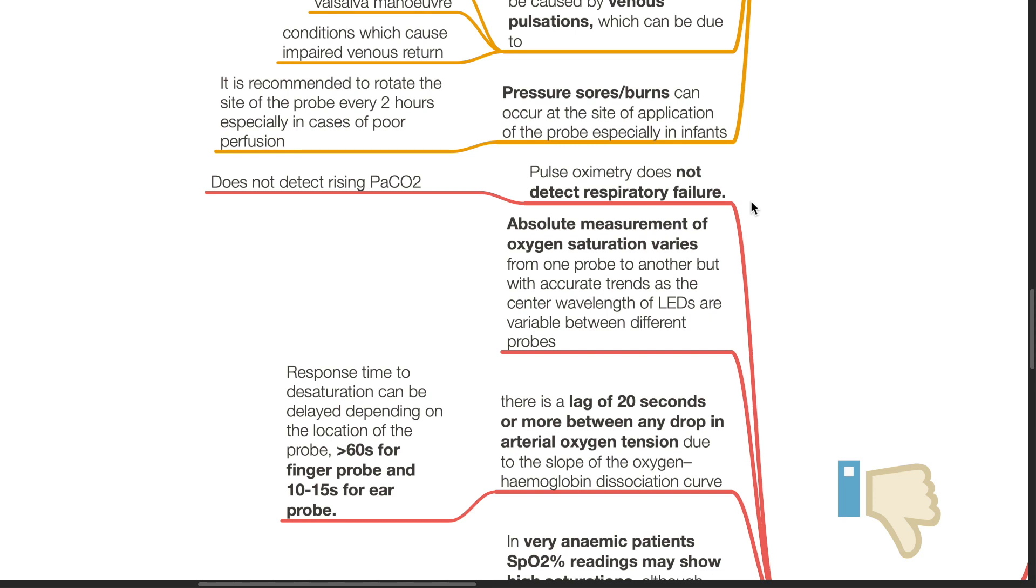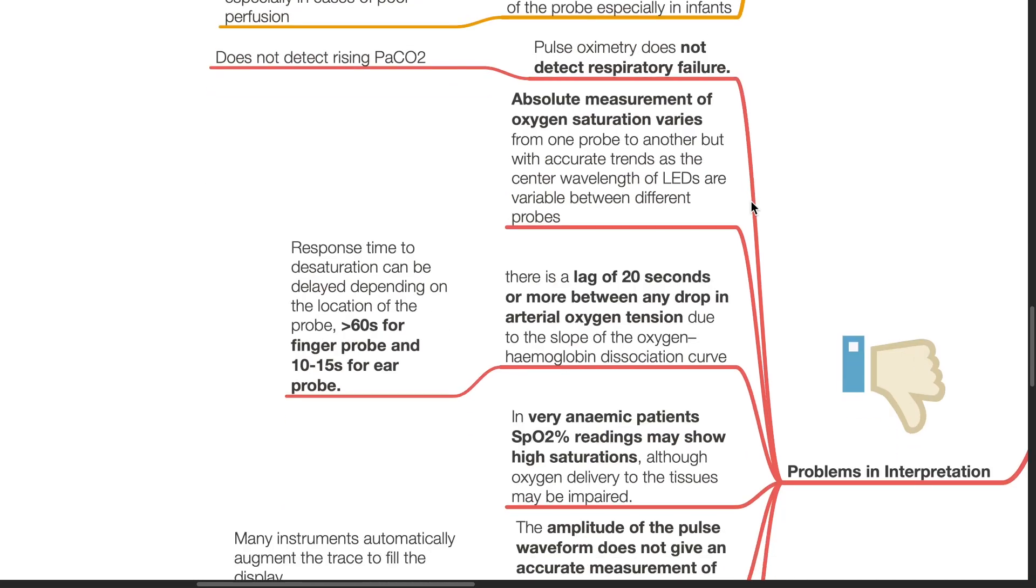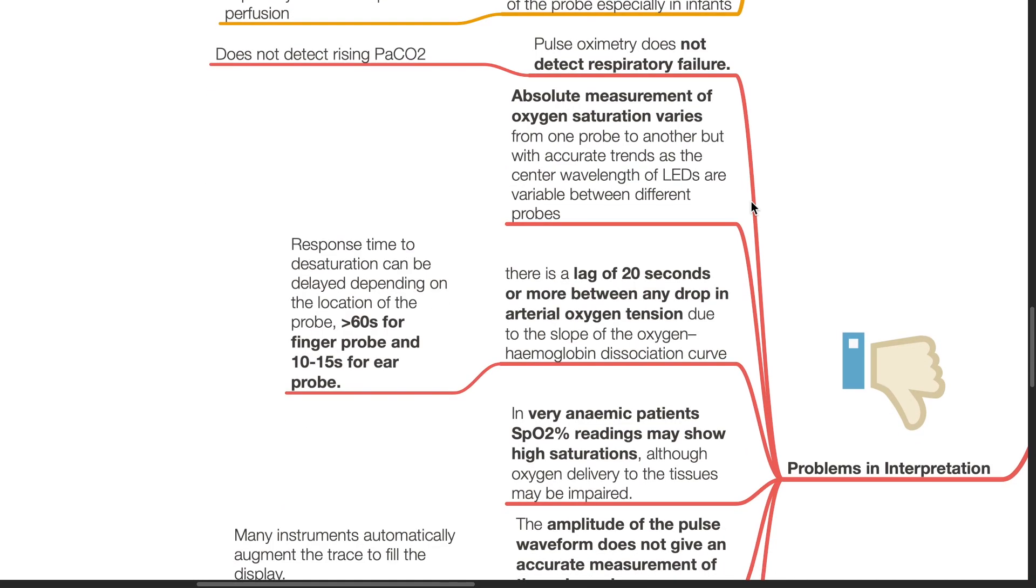The absolute measurement of oxygen saturation varies from one probe to another but with accurate trends as the center wavelength of LEDs are variable between different probes. There is a lag of 20 seconds or more between any drop in arterial oxygen tension due to the slope of the oxygen hemoglobin dissociation curve. The response time to desaturation can be delayed depending on the location of the probe. It can be more than 60 seconds for a finger probe and 10 to 15 seconds for an ear probe.